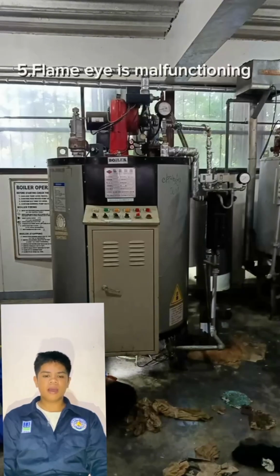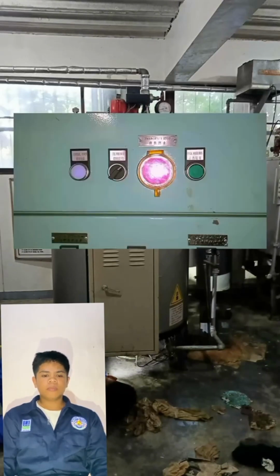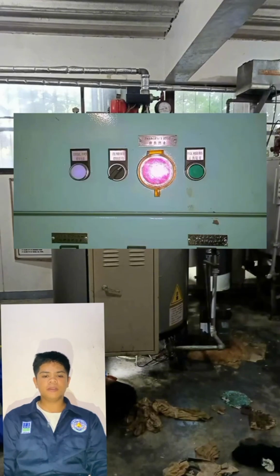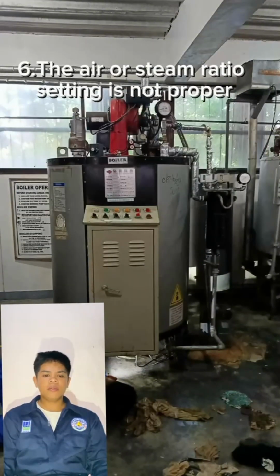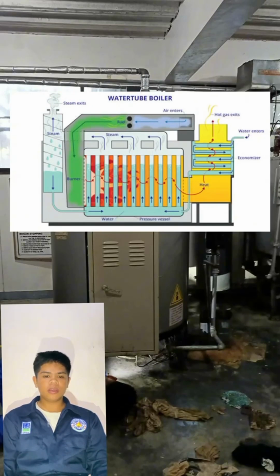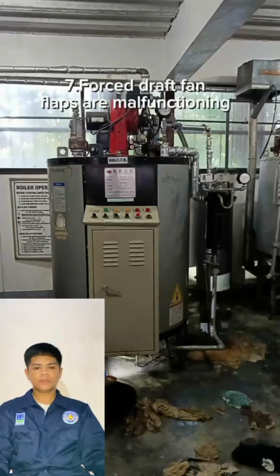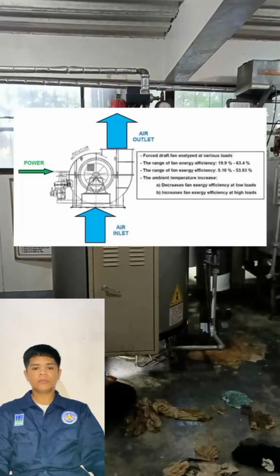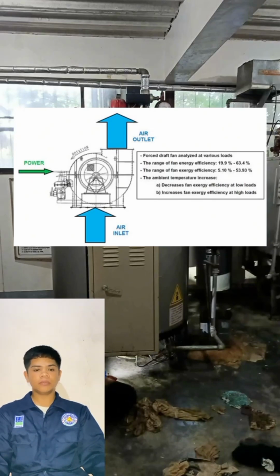The fifth is that the flame eye is malfunctioning. It is a photocell operated flame sensor fitted directly on the refractory to detect whether the burner is firing or not. And the sixth is that the air to steam ratio setting is not correct. For efficient combustion, the air to fuel ratio is very important. The seventh is that the forced draft valve flaps are malfunctioning. For removing excess gases trapped inside the combustion chamber, the forced draft fan or FDF is used for pre-purging and post-purging operation.